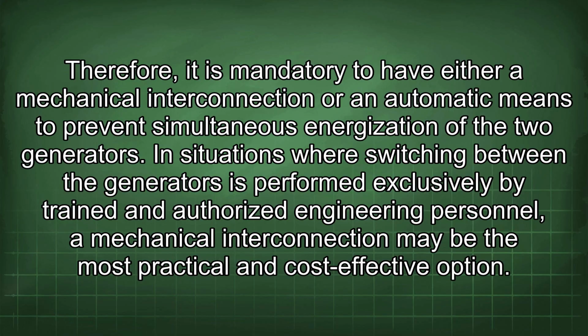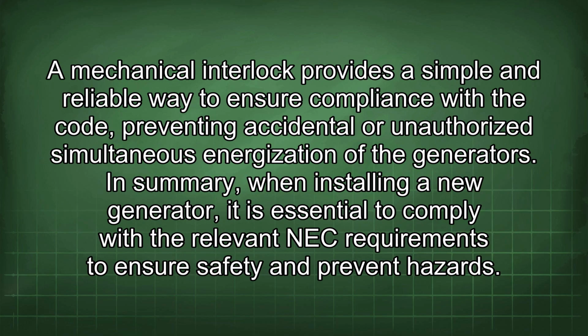two generators. In situations where switching between the generators is performed exclusively by trained and authorized engineering personnel, a mechanical interconnection may be the most practical and cost-effective option. A mechanical interlock provides a simple and reliable way to ensure compliance with the code, preventing accidental or unauthorized simultaneous energization of the generators. In summary, when installing a new generator, it is essential to comply with the relevant NEC requirements to ensure safety and prevent hazards.